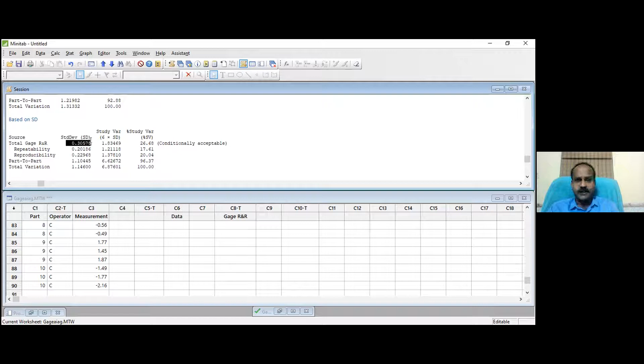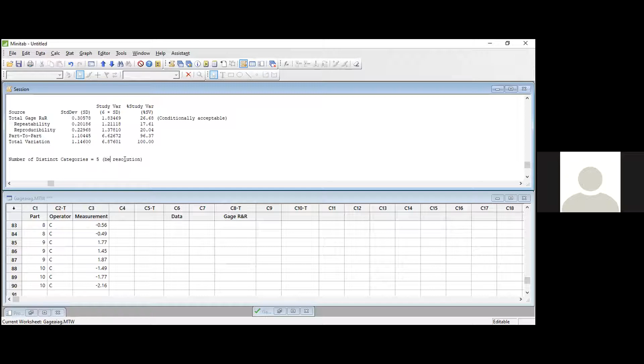What is the guideline for NDC? It should be minimum 5 or more than 5. If it is less than 5, what will you do? Because with less than 5, you are not supposed to use the data. Then what will you do? You must increase the resolution. Go for an equipment with a better resolution, and then your NDC will improve, right?